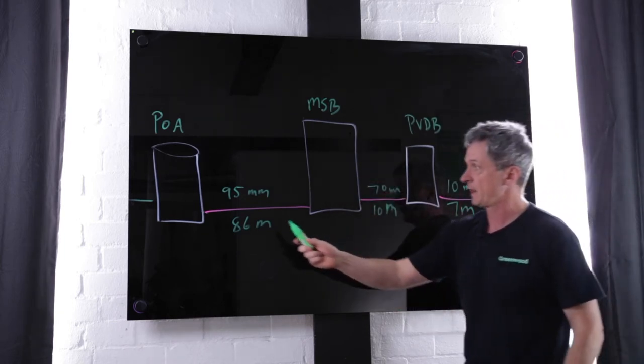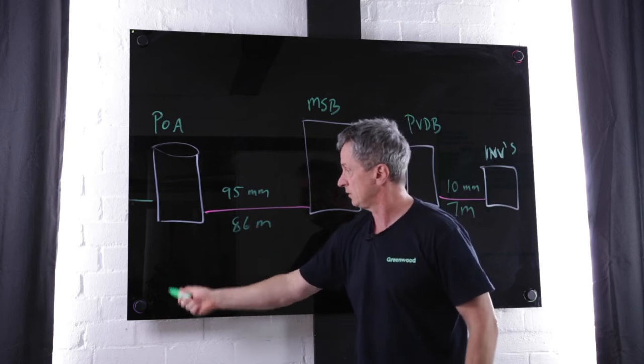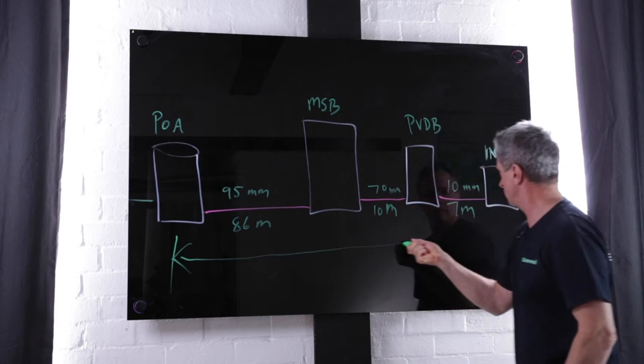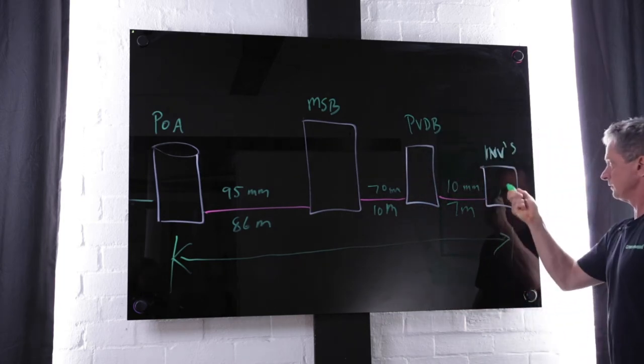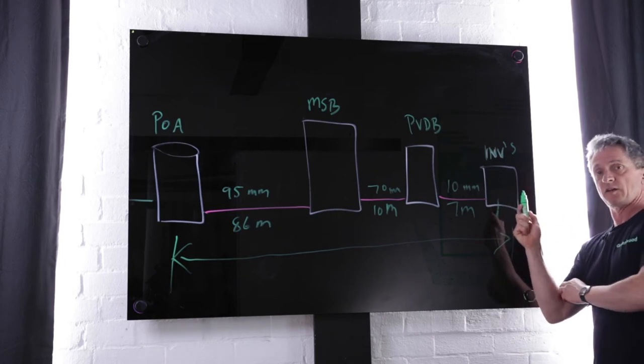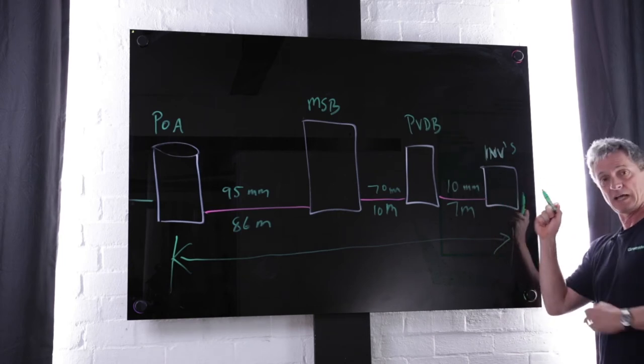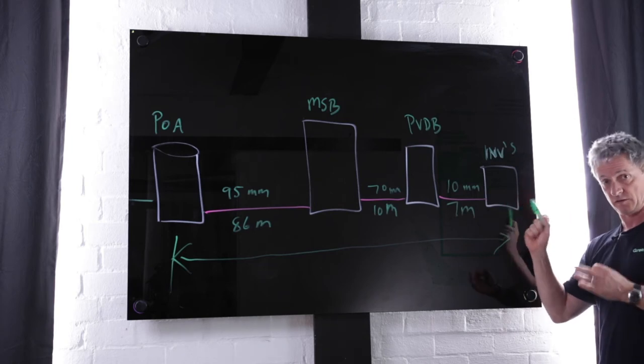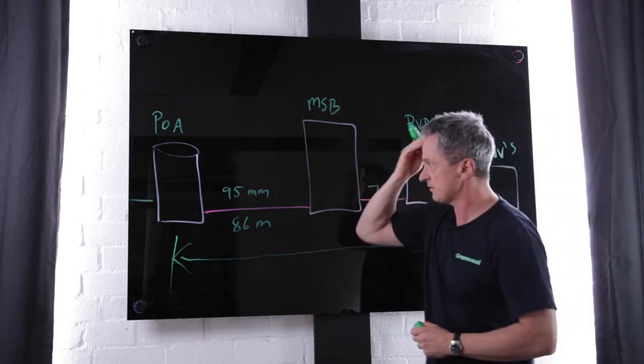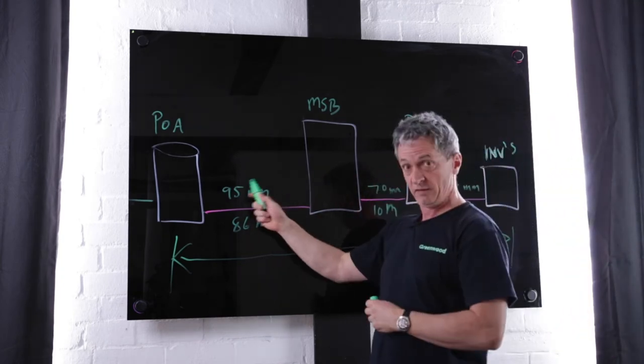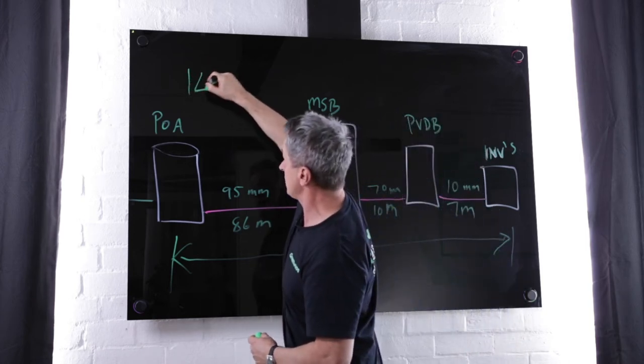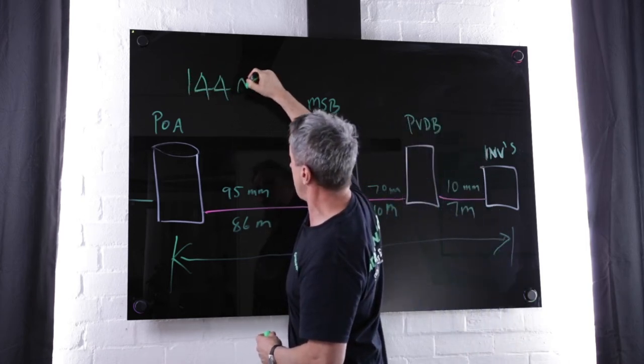We're talking about from the point of supply all the way over to the last inverter. If you have multiple inverters, you'd be doing the calculations on the largest capacity inverter that's furthest away. The first thing is to ascertain what the cable is and whether it can carry the current — in our case about 144 amps per phase.